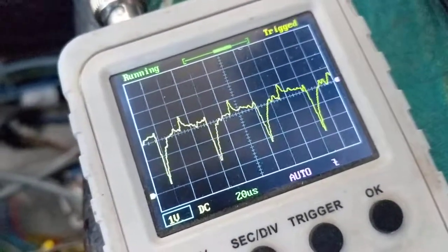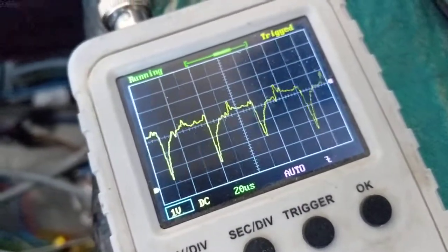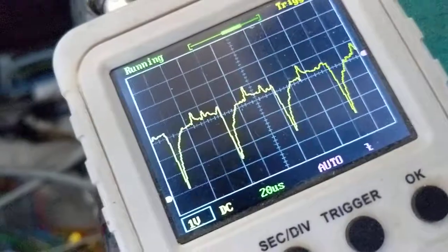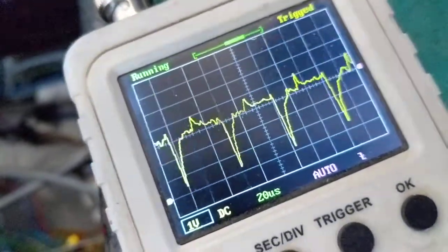So I think it's only that when these step-downs start, they start up and then they are confronted with this ripple. Then they also get trouble but they overcome the trouble.